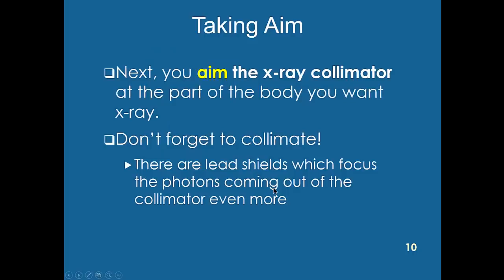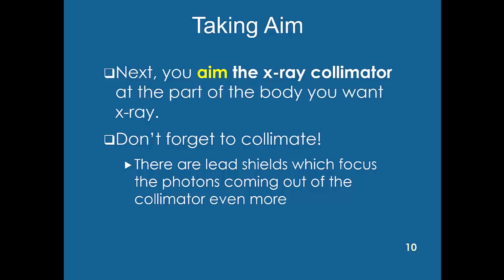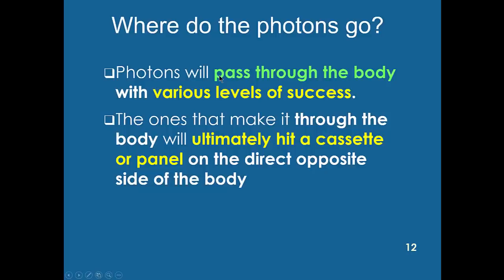You aim the x-ray collimator at the part of the body you want to image. Collimation means moving the lead shields in to narrow the focus of the beam of photons. In this example, the tube is aimed right at the lumbar spine. There are settings like KVP, mAs, and time. The photons come out and pass through the lumbar spine; you need something to capture the photons on the other side — it used to be radiographic film, but now there are photosensitive plates.